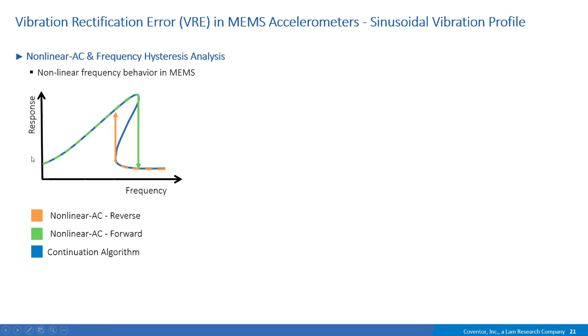So to study vibration rectification error, what you will do is run a nonlinear AC. For an accelerometer, you tend to do it on top of something you want to sense, so 1G. Here, if you want to sense Earth's gravity, on top of it you will put an AC excitation, at one frequency, as we said previously, with an amplitude in G, so G0. Additionally, you will want to study the scale factor with a regular DC analysis with 1G.